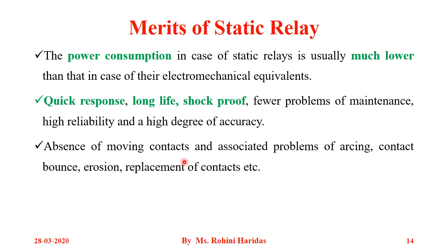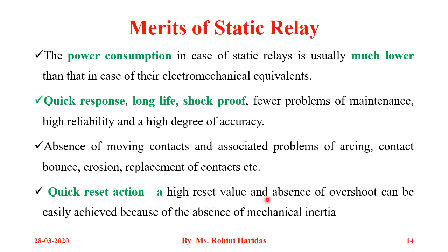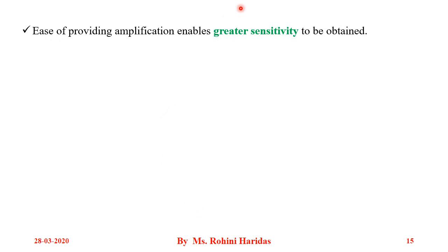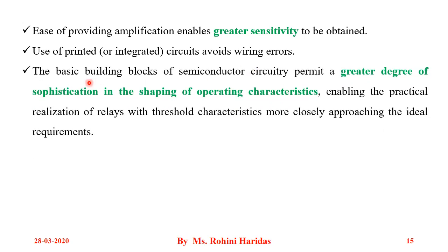The absence of moving contacts eliminates associated problems of arcing, contact bounce, erosion, and replacement of contacts. Quick reset action is possible — a high reset value and absence of overshoot can be easily achieved because of the absence of inertia. Ease of providing amplification enables greater sensitivity. The use of printed or integrated circuits avoids wiring errors. The basic building blocks of semiconductor circuits permit a greater degree of sophistication in shaping the operating characteristics, enabling practical realization of relays with threshold characteristics more closely approaching the ideal requirement.